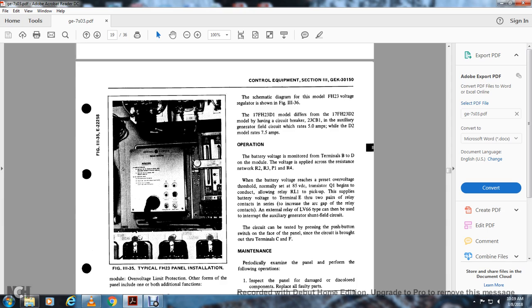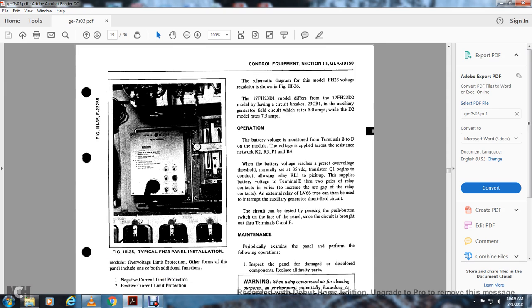The battery voltage is monitored at terminals B and D on the module, with the voltage applied across the resistance network of R2, R3, P1, and R4. When the battery voltage reaches the preset voltage threshold, normally set at 85 volts DC, the transistor Q1 begins to conduct, allowing the relay RL1 to pick up and supply the battery voltage from terminal E through two pairs of relay contacts in series. This creates an arc gap of the relay contacts, and an external relay of the LV66 type can be used to interrupt the auxiliary generator shunt field circuit. The circuit can be tested by pressing the push button switch on the face panel, with the sense of the circuit brought out through terminals C and F.